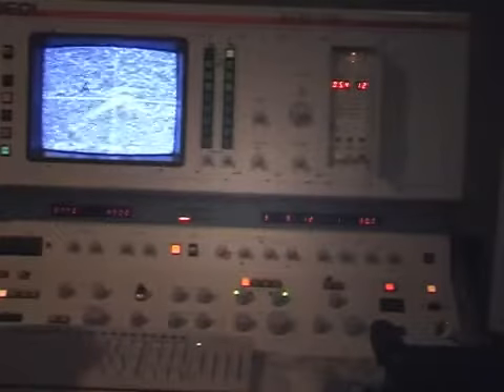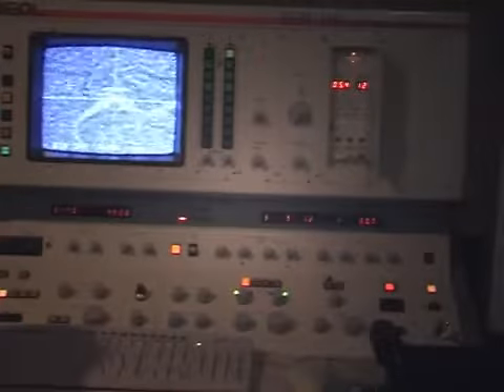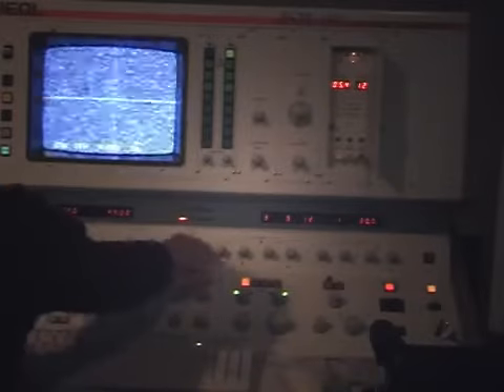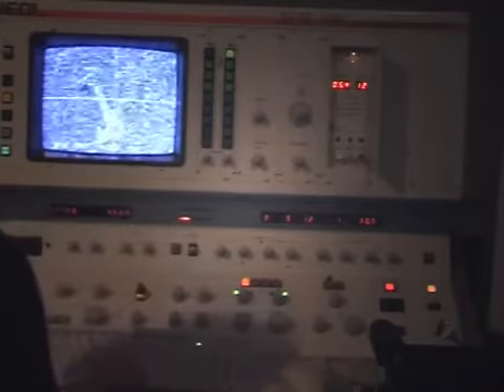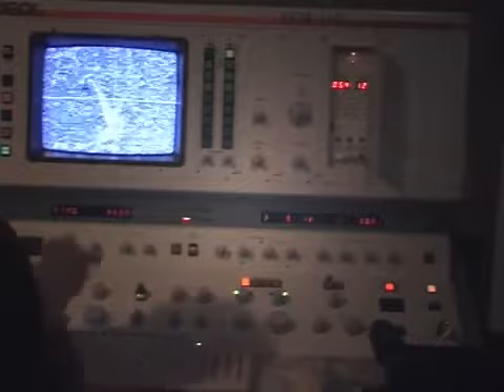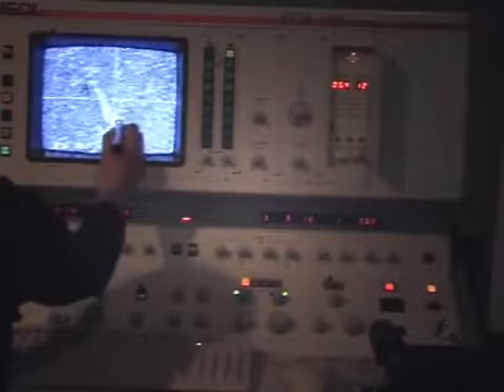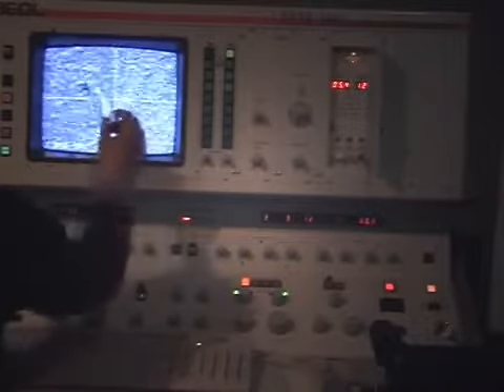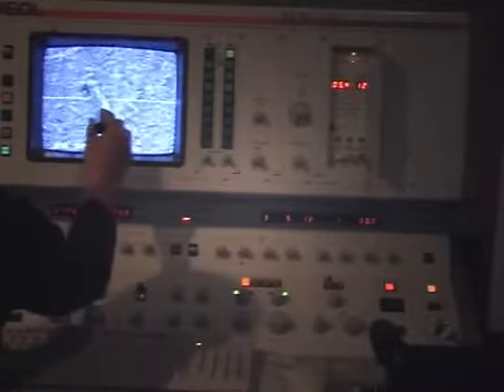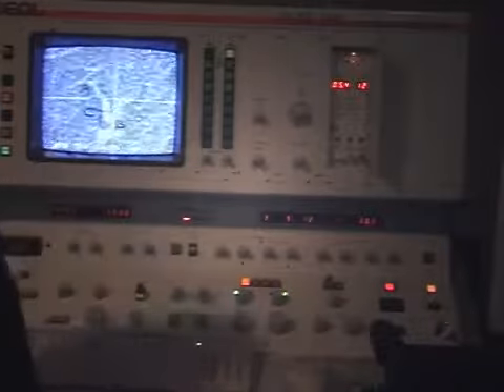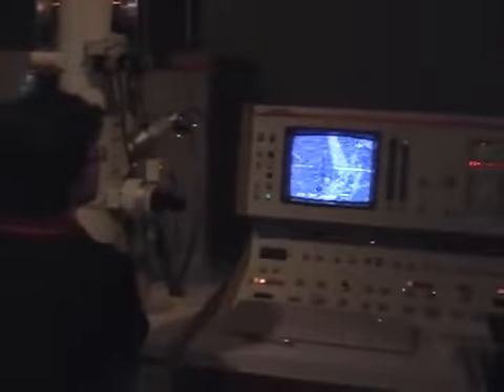Recenter the feature at point O with the specimen translators. Press objective pole button, apply lens clear for 1 second. The feature which was at point O is now at point B. Mark point B using a whiteboard marker. Use the specimen translators to move the feature to the point where the perpendicular bisector of OA intersects the perpendicular bisector of OB. Use the CL alignment XY shift knobs to return the feature to the center of the screen.